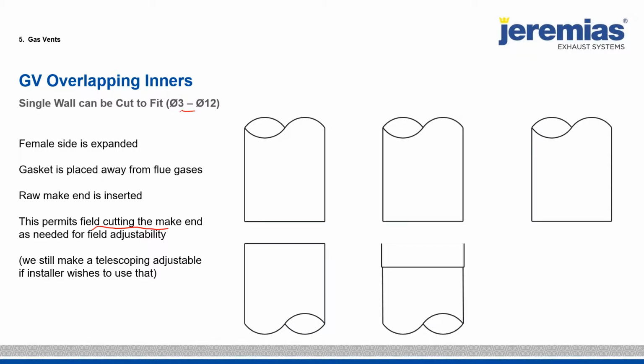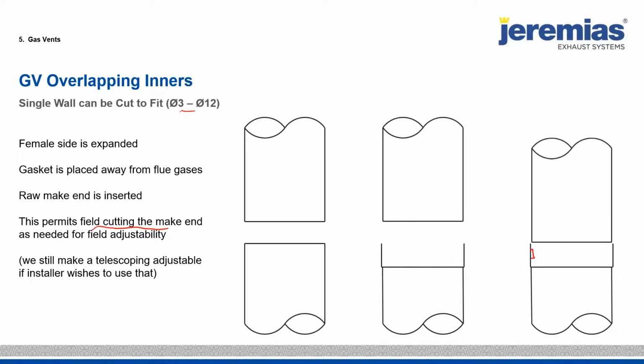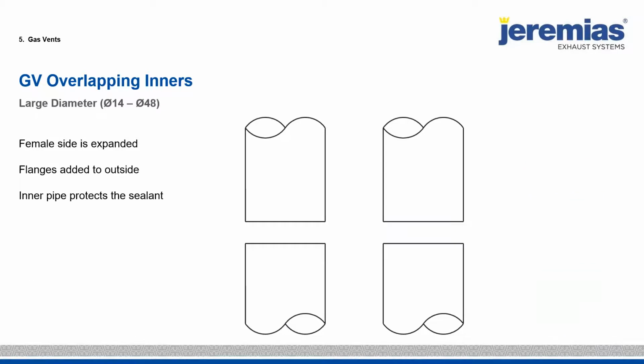So we expand the female side, we add a gasket right here. So it just simply pushes in, you have that full 2-inch overlap. This is important because the pipe can be cut to fit in the field. Contractors love this system. They can just go pick up a handful of 4-foot pipe lengths and some elbows, and they can just cut the lengths to fit in the field. And that's also better for the product as well. And the less joints you have, the better you're going to be.